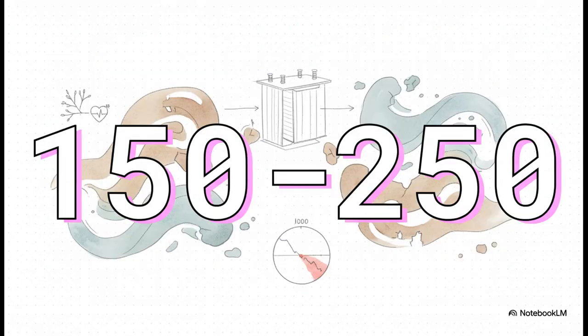And this science gets incredibly precise. It's not just the oil, they're also tracking the health of the special paper insulation inside. Its strength is measured by its degree of polymerization, or DP. Brand new paper has a DP of around 1,000, but when that number drops down to between 150 and 250, that paper becomes brittle. It's at an extremely high risk of just failing. Knowing that number is like a doctor knowing a patient's final prognosis.